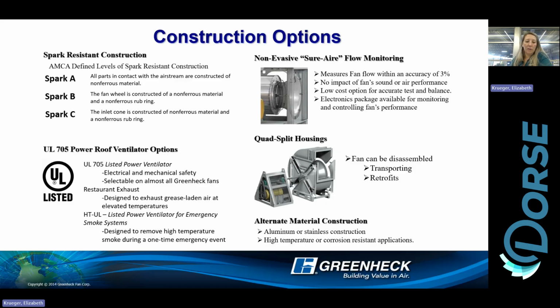Those different levels of spark resistance are based on what is actually needed. So if you're exhausting maybe a storage room that stores some solvents or some other sort of chemicals, maybe your spark resistance requirements aren't as high. Then you'd go with a Spark C. Spark C would be just the inlet cone of the fan made out of aluminum. Spark B is the next level up. With Spark B, we would make the wheel out of aluminum. Spark A is the highest level of spark resistance. That's the entire airstream, so the entire scroll, the entire wheel, and inlet cone are all made out of that non-ferrous, non-sparking material.